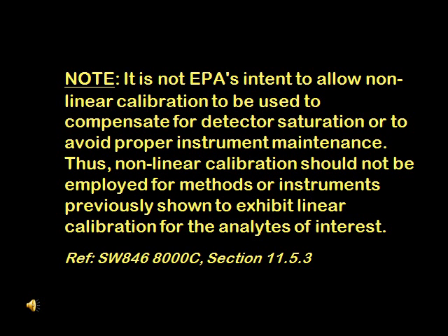A note of caution is placed in 8000C concerning the use of nonlinear calibrations. A nonlinear model should not be used to compensate for detector saturation or to avoid proper instrument maintenance. The nonlinear calibration should not be employed for analytes if they have shown to be linear in the past using a particular instrument or method.